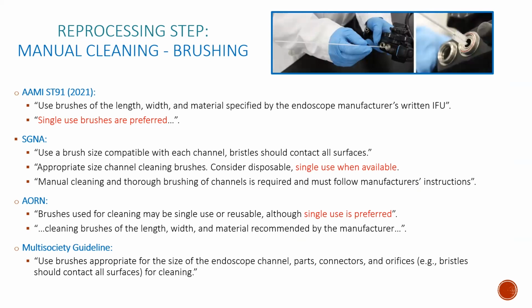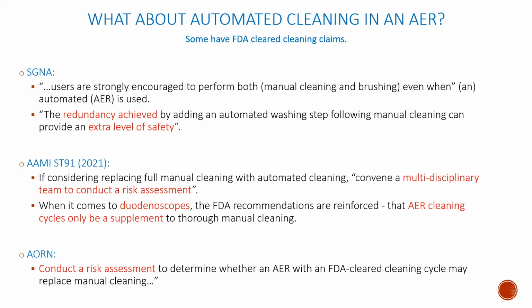All organizations continue to emphasize manual cleaning as critical to successful reprocessing. SGNA refers to it, for example, as the most critical step in removing bioburden. All organizations stress the need to have brushes that are compatible for the lumen size. SGNA, AAMI, and AORN state that single-use brushes are preferred. Increasingly, we have the existence of automated endoscope processors, or AERs, with automated cleaning claims. SGNA strongly encourages maintaining manual cleaning and channel brushing, even prior to AERs with cleaning claims. They emphasize that such redundancy provides an extra level of safety. AAMI and AORN recommend performing a risk assessment if considering foregoing some or all of manual cleaning. And remember, for duodenoscopes, full manual cleaning is still required for the IFUs as well as FDA direction.